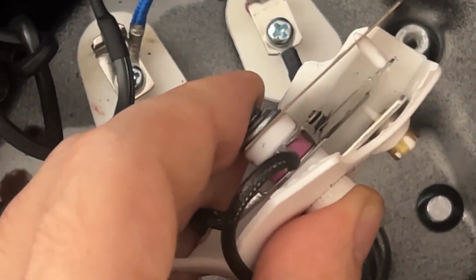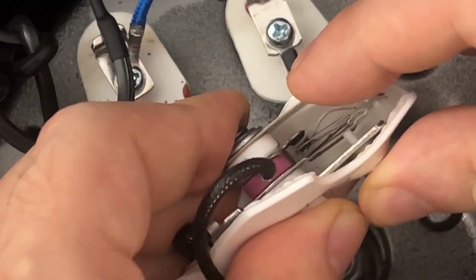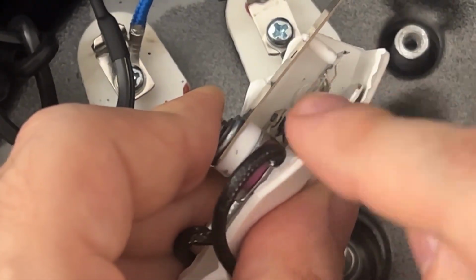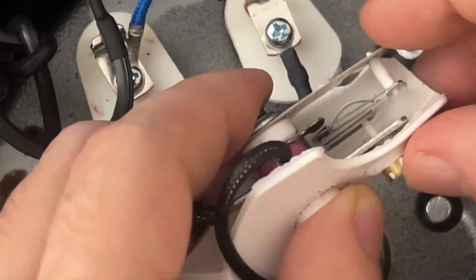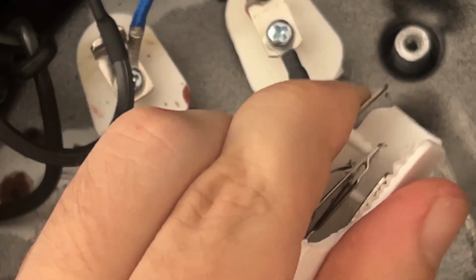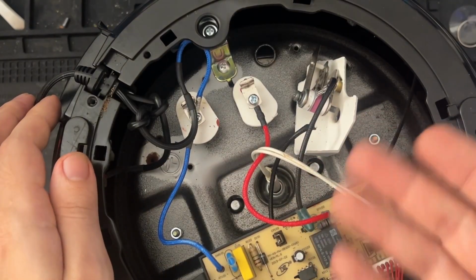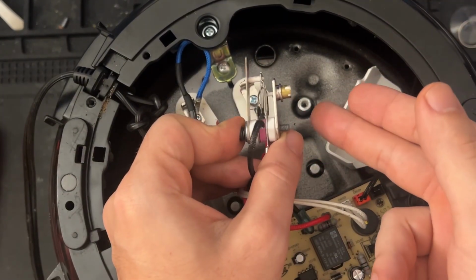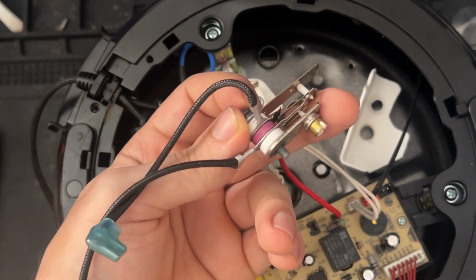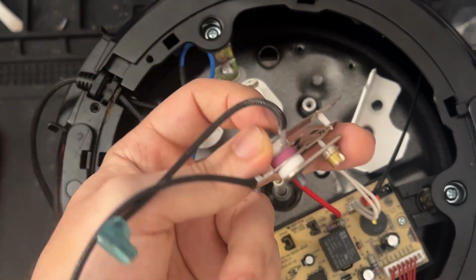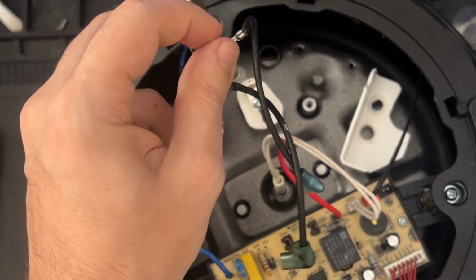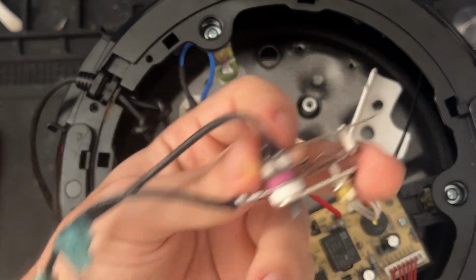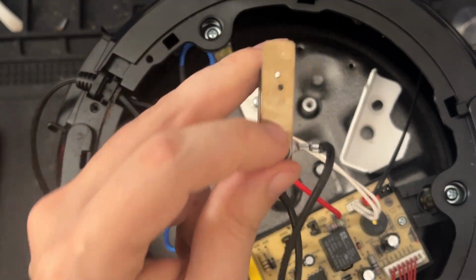While holding the assembly in place, I will press down on the sensor to open up the contacts and then spray electrical contacts cleaner inside, squeezing it back and forth to clean it up and letting it sit for a while until it dries. From here, we can reinstall the pressure sensor and test it for functionality. So that should have been enough to get this sensor working again. However, in my case, unfortunately, continuity is still good on the wires. The sensor itself is toast. So it's going to need to be replaced.